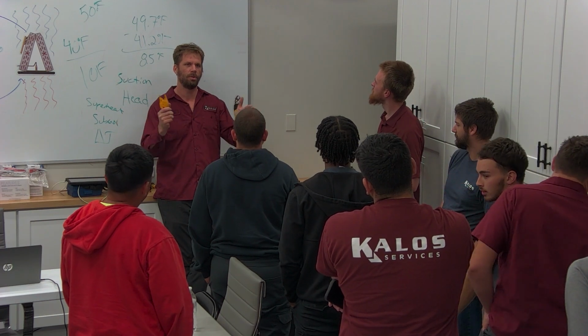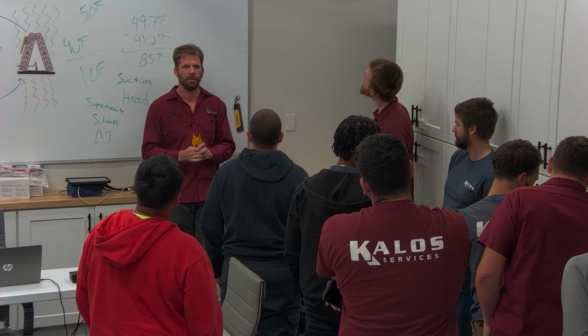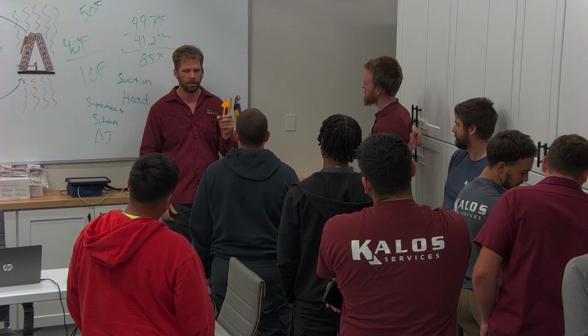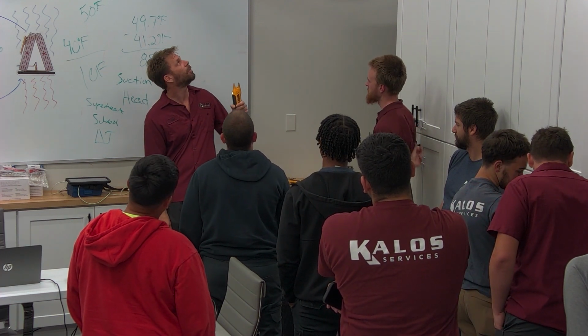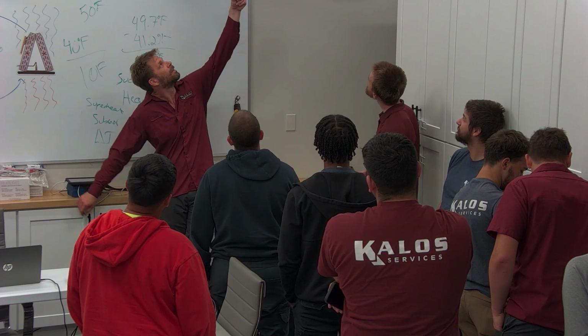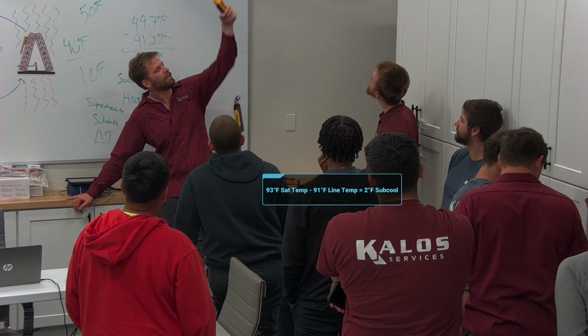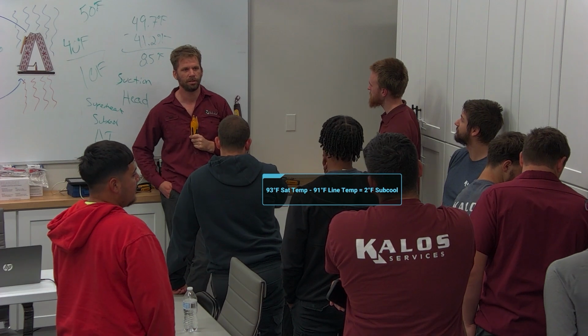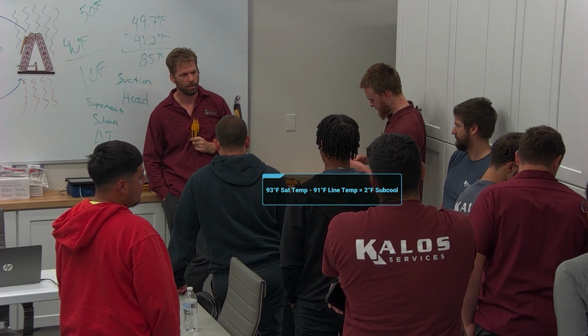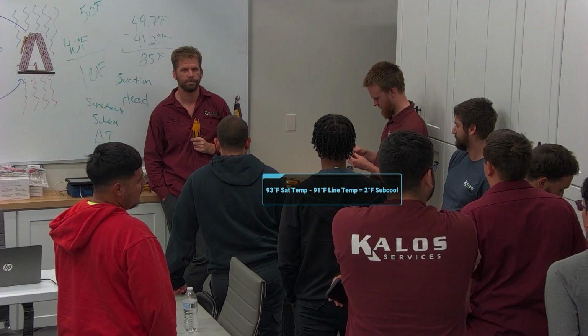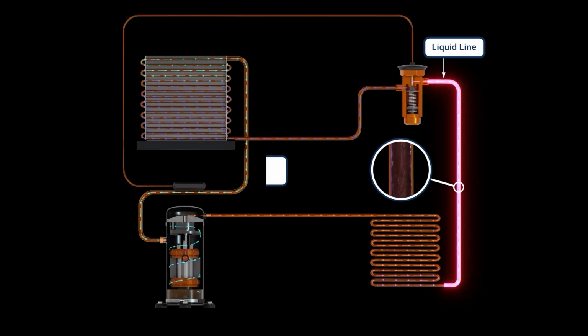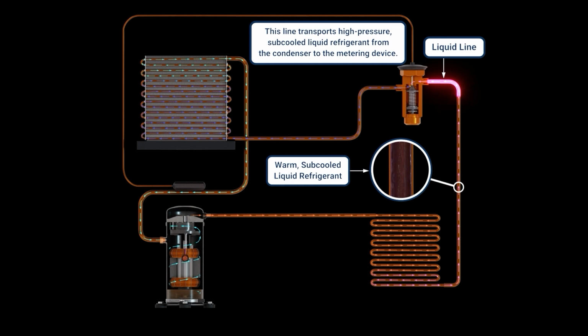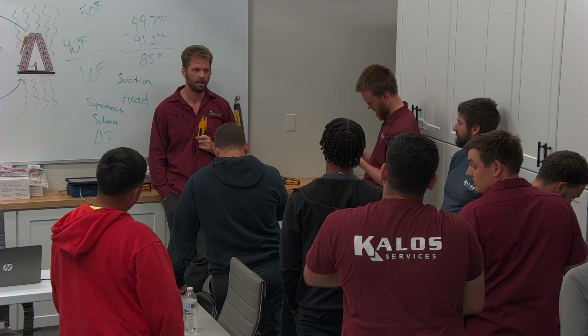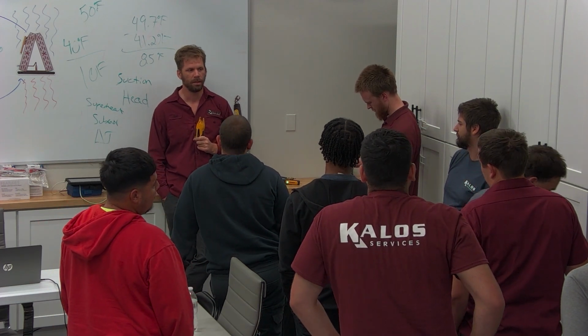We never have a liquid line colder than outdoor, because the outdoor is what cools off the refrigerant. So I was holding it in here, it was colder, one labeled. But the point is, I want you doing the math. 91 is the line, 93 is the saturation. Is that refrigerant all the way liquid inside that line? Yeah. We've proved it by 2 degrees. It was all the way liquid when it was just 1 degree below saturation, and now it's 2 degrees below. We know it's all the way liquid.